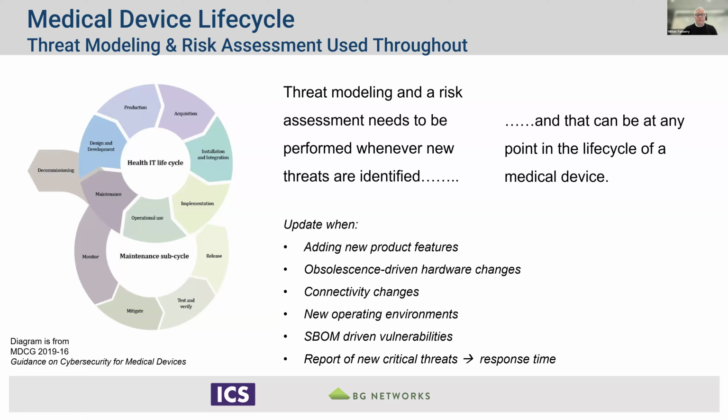So basically, this would give you a report of new critical threats, and the thing to keep in mind here is the response time. As part of the requirement from the FDA is not just that you fix these things, but that the timing on the fix is proportionate to the threat it poses.